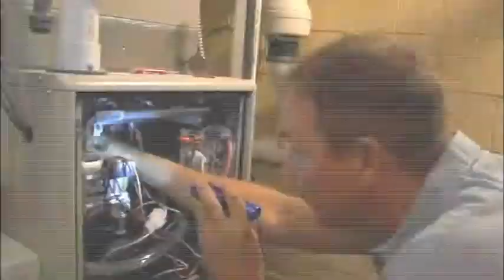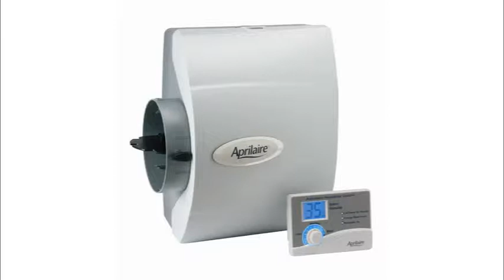The burners are pulled out and cleaned because they can get dusty and rusty. The technician will check the heat exchanger carefully, especially on an older furnace, to make sure it is safe. And they can also brush out the heat exchanger of an older furnace and vacuum out any soot or rust or dirt that's accumulated over the year. Once the burners are back assembled, we'll check the blower to make sure the blower is clean, the motor doesn't have dirt built up on it. Then they will check the condensate drain of a 90% furnace to make sure that is clear.